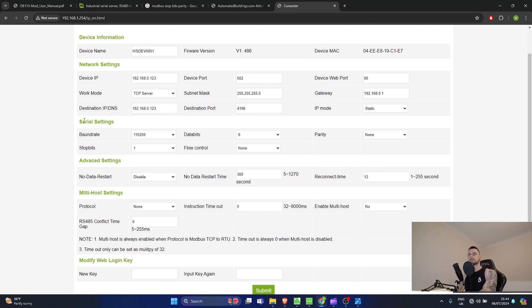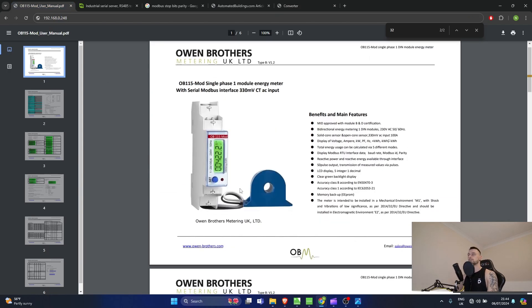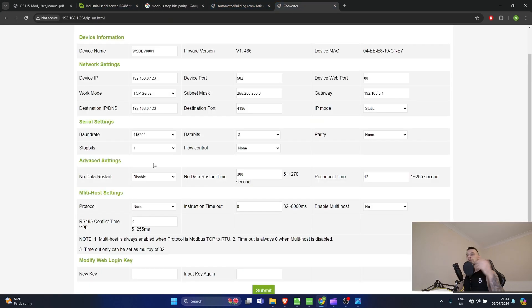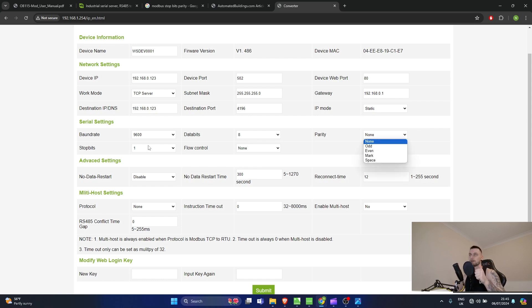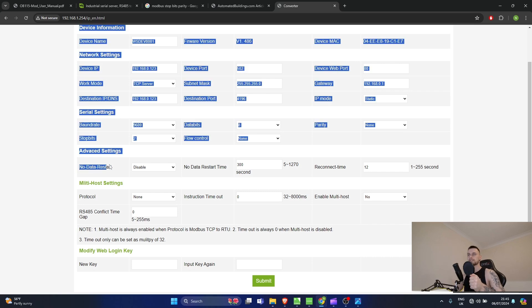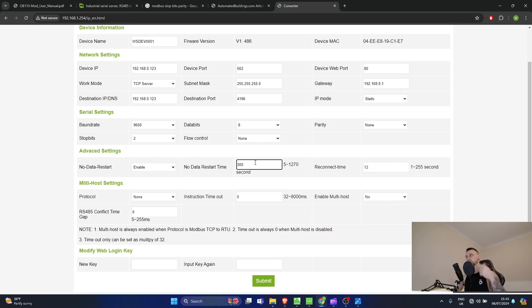Now the serial settings - these are the actual settings of your connected device. Going back to the OB meter, I know the defaults: baud rate 9600, parity none, and stop bits two. So I'll adjust the settings here accordingly. Data bits are almost always eight, so I'll leave that as eight, no parity, two stop bits. Flow control we don't need for this device - check your datasheet for others. I'll also enable the reconnect option so if there's no communication for 300 seconds it will try to reconnect and reboot itself.